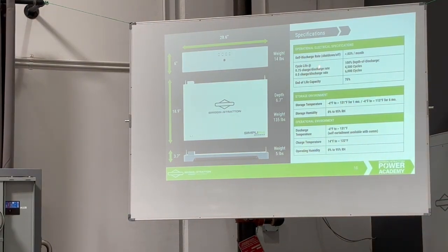And Nathan, if we slow it down a little bit, so it's a 2-hour charge, 2-hour discharge, we're looking at 6,000 cycles. Just to give you an idea, isn't the Powerwall 3's charge rate still 5 kilowatts? Yeah. So we're looking at about 2.7, roughly 3 hours to charge that battery. Right, so we can charge a lot faster than the Powerwall 3. On discharge, the Powerwall 3 is there with us, but on the charge side, we can charge faster.